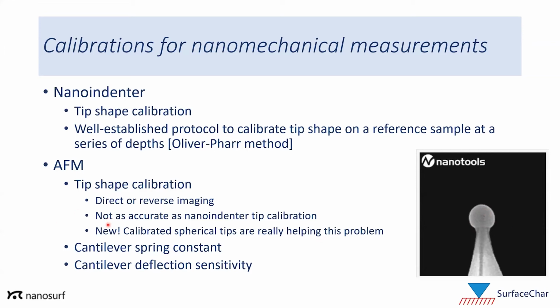And in addition to tip shape, you have to calibrate the spring constant and the deflection sensitivity, which are kind of standard for all nanomechanical measurements with AFM.